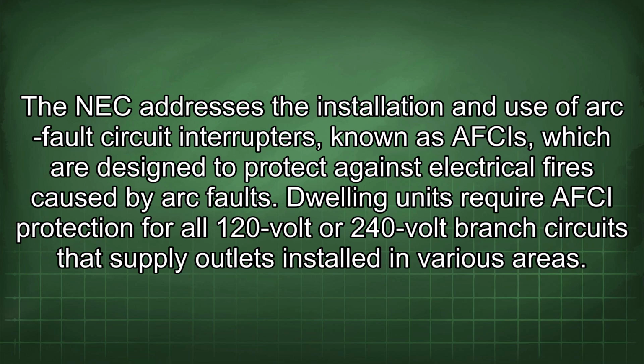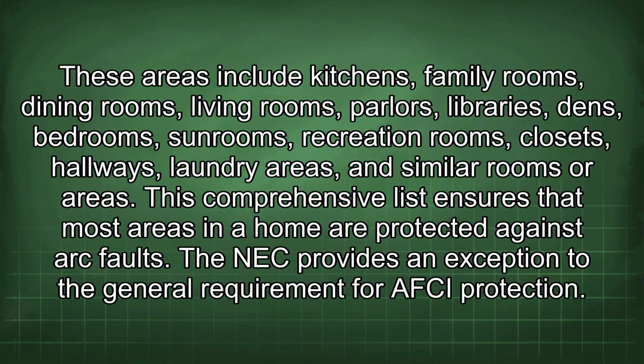The NEC addresses the installation and use of arc fault circuit interrupters, known as AFCIs, which are designed to protect against electrical fires caused by arc faults. Dwelling units require AFCI protection for all 120 volt or 240 volt branch circuits that supply outlets installed in various areas. These areas include kitchens, family rooms, dining rooms, living rooms, parlors, libraries, dens, bedrooms, sunrooms, recreation rooms, closets, hallways, laundry areas, and similar rooms or areas. This comprehensive list ensures that most areas in a home are protected against arc faults.